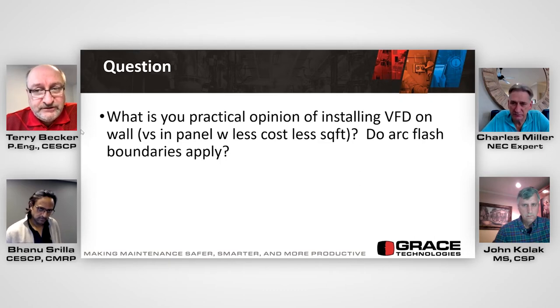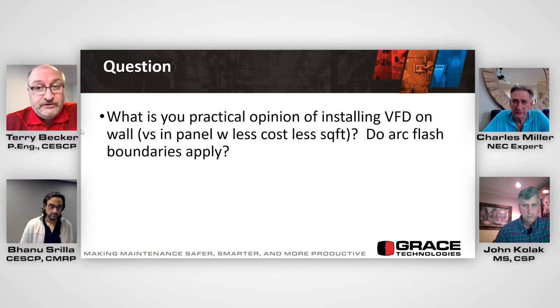It's when we're doing a work task, as per table 130.5(C) in 70E or table 2 in Z462, that we evaluate the condition of maintenance and then the likelihood of occurrence of an abnormal arcing fault, yes or no. But you need to do a risk assessment against that decision. In some cases, if we have abnormal equipment conditions that you identify in real time when you approach the equipment, and you see evidence of impending failure on a wall-mounted VFD, then you're going to turn the power off immediately. So we need to start by saying energized electrical equipment is in a normal equipment condition, and we don't need arc flash PPE to operate it, stand in front of it, or be around it.